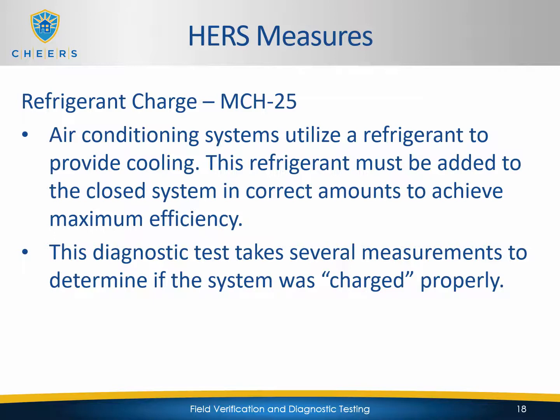But this charge can also be affected by the metering device, which we'll get into when we get into the actual refrigerant charge section, as well as the airflow across the coil. Depending on the coil design and where the ductwork is located, sometimes that can affect whether or not the system can achieve the proper charge. So we're going to be measuring that charge, taking some temperature measurements, as well as the airflow. Airflow goes along with this as well. If we don't have enough airflow across that coil, then it's not going to be able to be charged properly. So we're going to test the airflow as well.